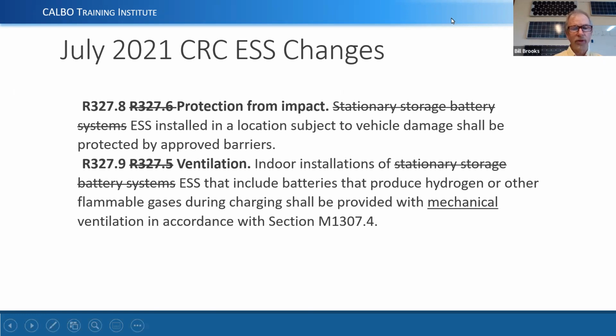ESS that includes batteries that produce hydrogen or other flammable gases during charging under normal conditions, and the only products that do that would be flooded lead acid batteries, shall be provided with mechanical ventilation. So the upshot is there are exactly zero UL 9540 energy storage systems that include flooded lead acid batteries. So this section of the code is essentially a moot point, because it is impossible to generate hydrogen or flammable gases under normal charging conditions. So that's the point here. This is not talking about abnormal conditions. That's why we have smoke alarms, heat alarms, all that kind of stuff for those kinds of situations.